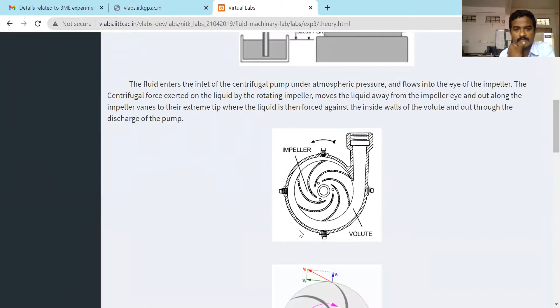One wheel is there on which impeller vanes are there. If you see the centrifugal pump construction, one part is the impeller wheel, which is mounted on the shaft. And on the wheel a series of curved vanes are placed. The second part is the casing. This casing covers the impeller part.